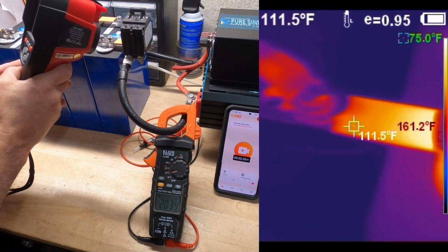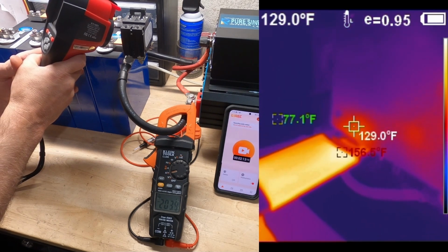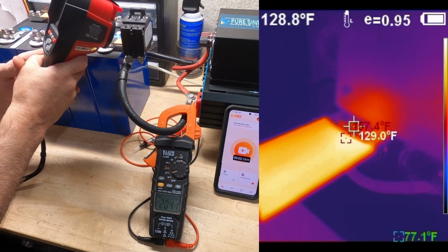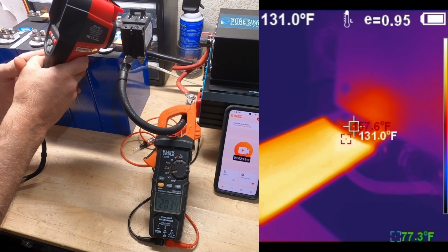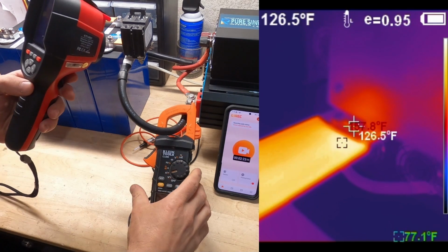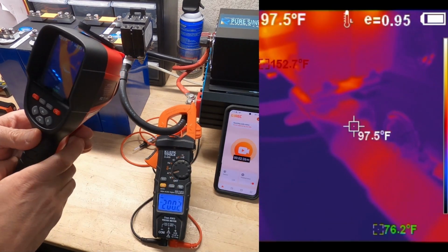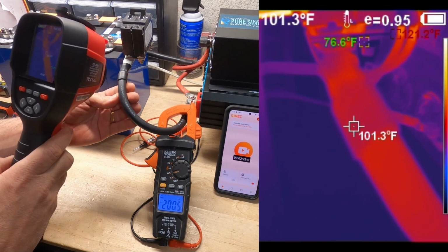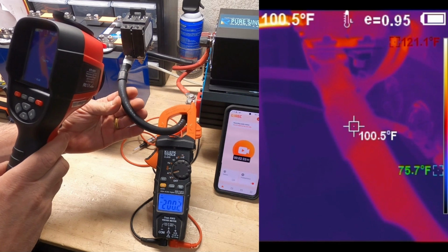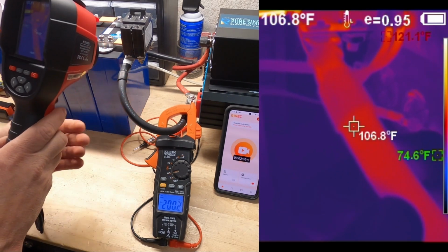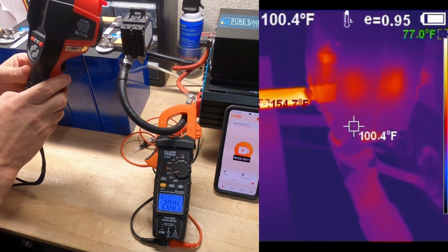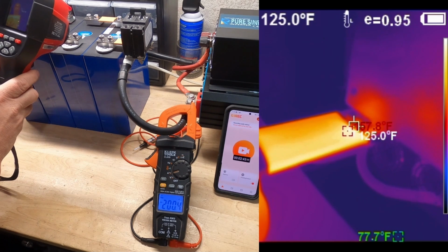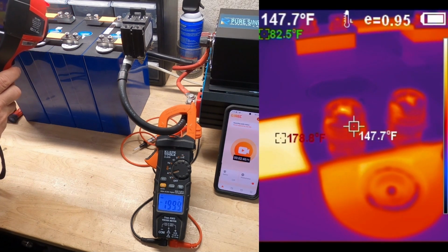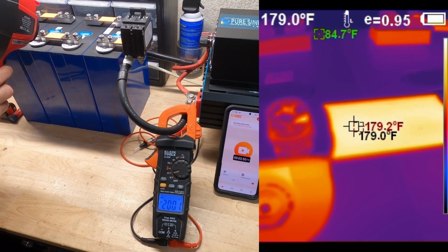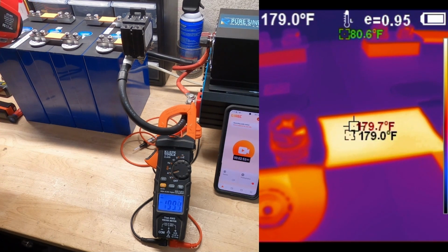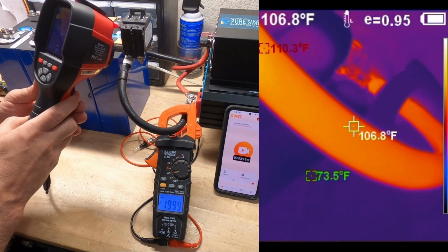Anyway, let's check the breaker. Breaker's at 130 near the contact. But the cable is doing pretty good. 106 degrees. I'd say the main problem right now is the studs themselves. The bus bars. 180 degrees. Let's check the lug on the cable.